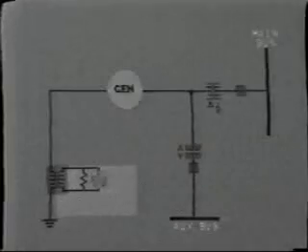Instead of a resistance, the impedance in the neutral will be provided by a transformer, the secondary of which is connected to the 59G relay. The grounding resistor is connected in the secondary circuit and sized typically between 100 and 200 ohms to limit the magnitude of fault current flowing through the neutral to 10 amps or less.